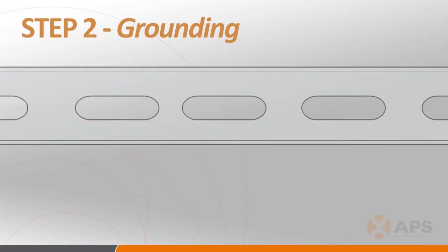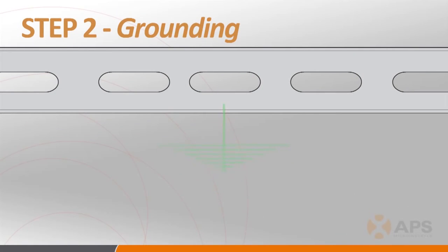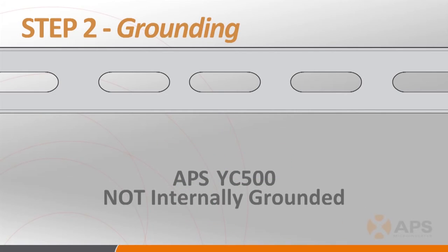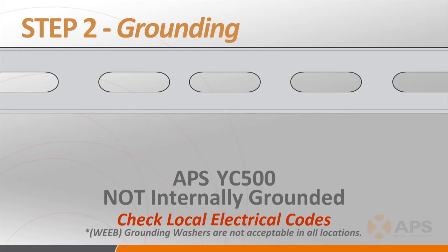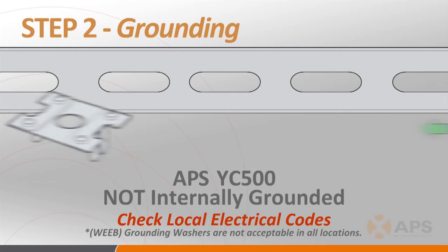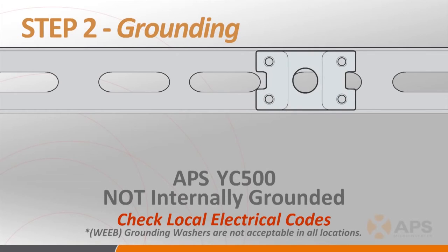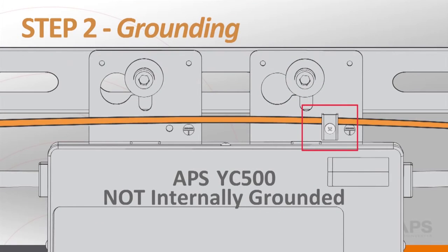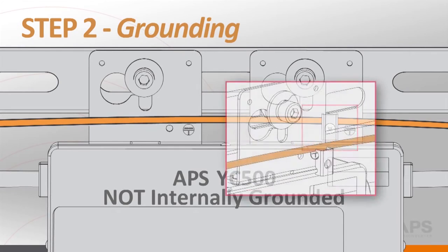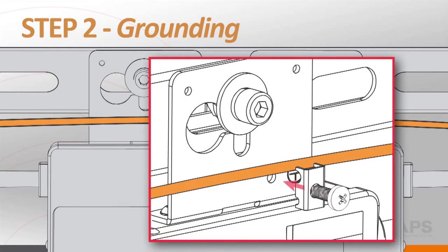Step 2 is making sure that the inverters are properly grounded throughout the system. The YC500 is not internally grounded within the chassis, so it requires an external ground. Depending on your jurisdiction — and it's always best to check with your local inspector — you can either use a grounding washer when attaching the inverter to the rail of a well-grounded racking system, or you can use the grounding lug on the YC500 to string bare copper wire to an appropriate system grounding location.